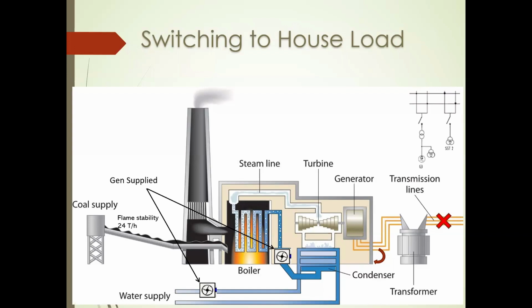So the OEM recommends that the plant should not operate in house load for more than 30 minutes. If you manage to operate this plant in house load for 30 minutes, the OEM does not recommend keeping it longer than that, and you have to reconnect it to the grid by resynchronizing it. You have to keep the boiler fire lit so that a very low steam supply is there. Of course, you have to use this bypass duct as well to control the steam line pressure, temperature, all these things.